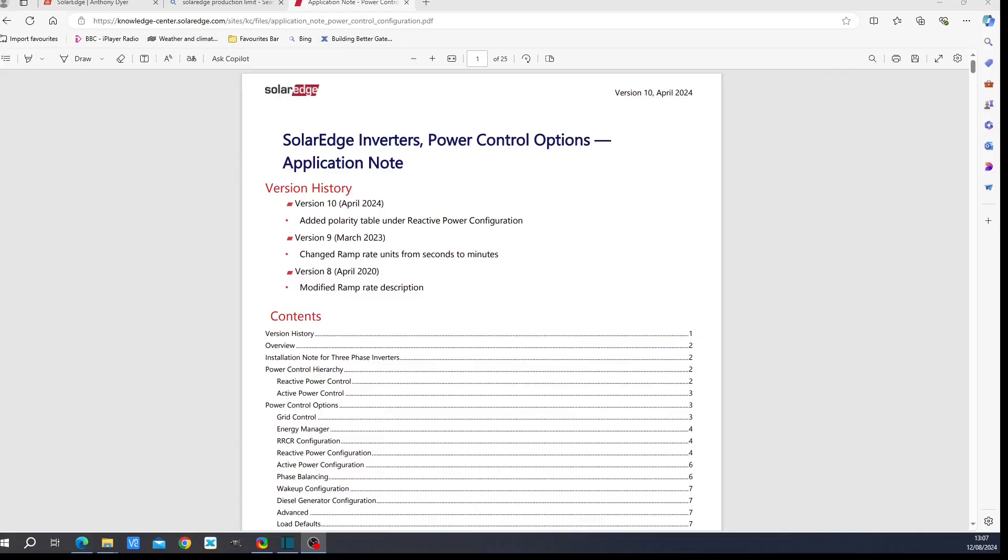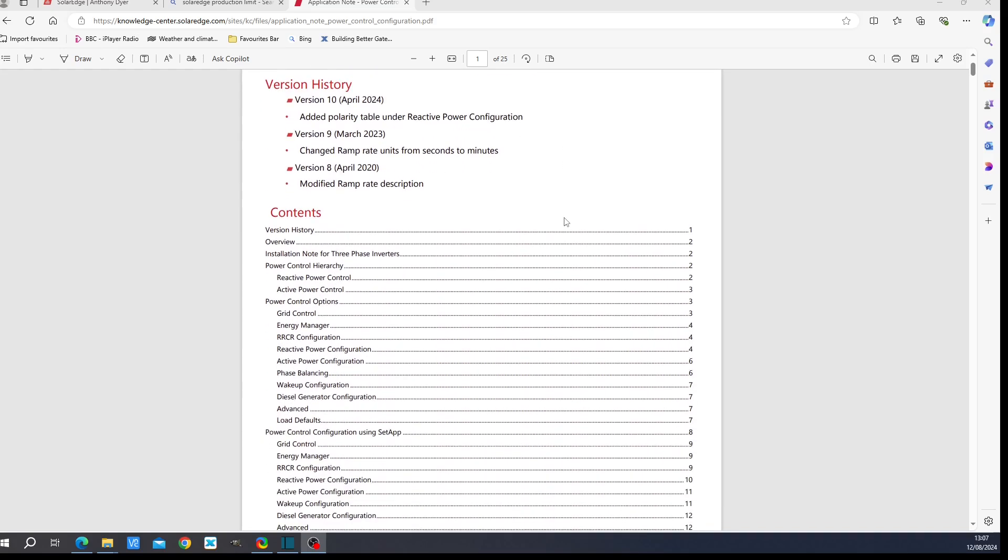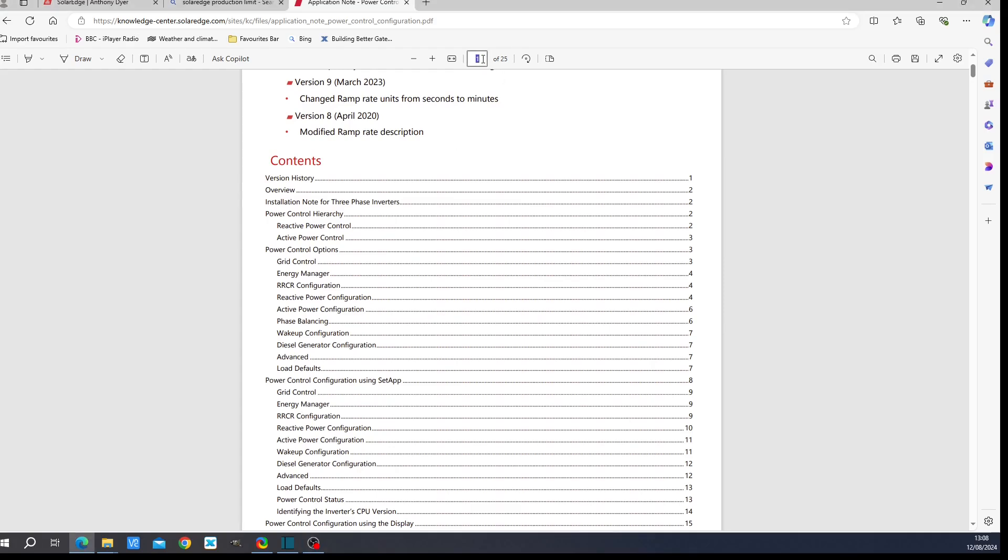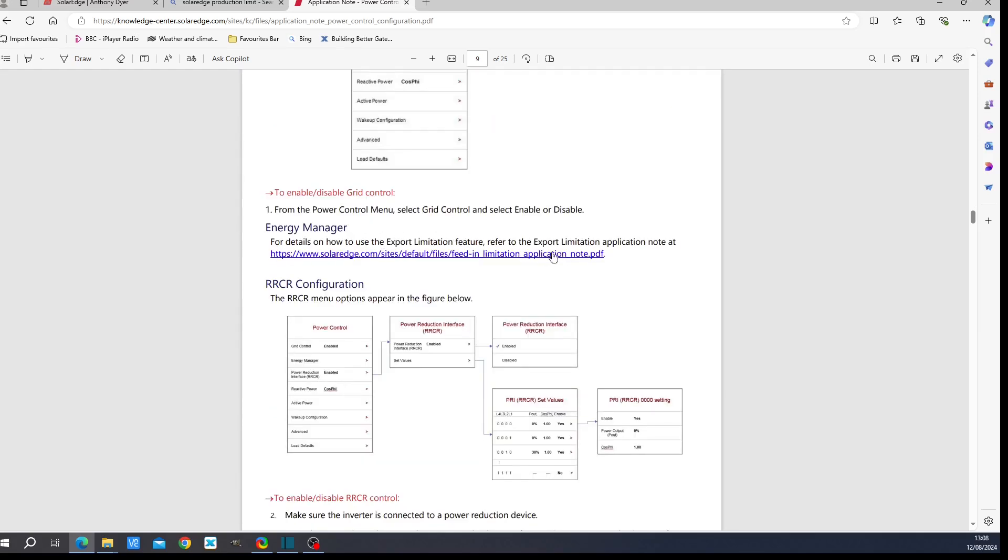Before I went into setup configuration, I did a lot of research into what was going on. We've got this application note for the SolarEdge inverters. As you can see, it's been updated relatively recently. This describes all the power control options that you have. As you've seen in the setup configuration, I have gone through the pertinent options. The active power control and the energy manager are the two relevant sections which have something to say about it. If we go to page 9, for example, there was no grid control there, which basically means the national grid does not command your inverter. That's not enabled. The energy manager, that's where we went to, and also the active power configuration. There is a specific application note for export limitation. As you've seen, 5 kilowatts is the limit on my site. That's got nothing to do with the 6.4 limit power production limitation.